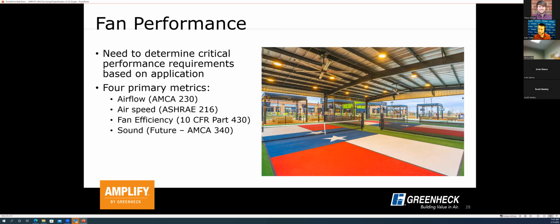Air speed is also very critical for these fans. Like we've talked about earlier in the presentation, air speed really dictates somebody's comfort level in a space. So there is a relatively new standard for testing and determining air speed, which is ASHRAE 216. Unfortunately, there is not currently a certification program available for this standard. So look, on your submittals or any information from an HVLS fan manufacturer, for something that says it was tested in accordance with, or per the procedures in, ASHRAE 216. That's about as best as you can get for this type of data currently. But there will hopefully be some development of a certification procedure to get third-party verification of data in the future.